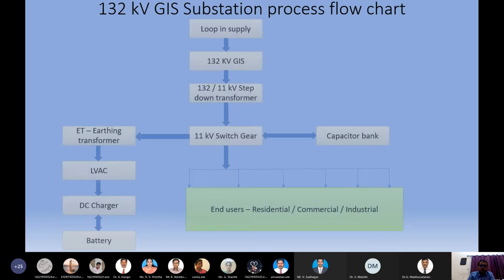So, the 132 kV GIS substation process flow chart. This is the main real theory which I was trying to give. The loop in supply, the so-called supply from a 400 kV substation. The first supply inlet, the feeder, will be the 132 kV GIS, which is the heart of the substation, where the power will be taken and controlled, and then carried over to 132 kV by 11 kV step-down transformers, where the power supply will be stepped down from 132 kV to 11 kV for commercial uses. And from the 11 kV transformers, it will be transferred to the 11 kV switchgear, where the control is there for the direct end users, as we said, residential, commercial, industrial, or whoever it might be.